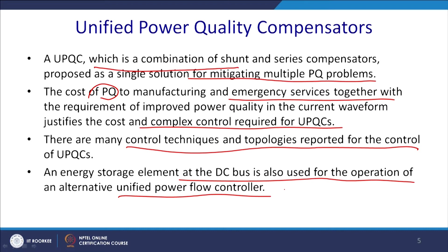DSTATCOM and DVR are controlled separately for power quality enhancement for current and voltage respectively. DSTATCOM is for current harmonic mitigation and other current related issues, and voltage flickers, voltage harmonics, voltage sags or swells are the part of the DVR. Most of the control algorithms reported for the DSTATCOM and DVR are applied for the UPQC. Essentially, you put separate processing units for the STATCOM and DVR, and it should work. But there is a little change of the control circuit when you are using it in a unified mode.